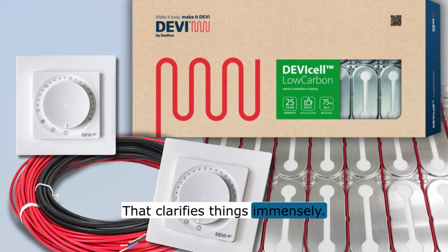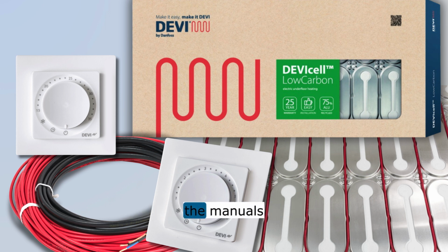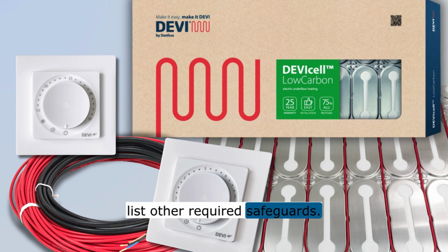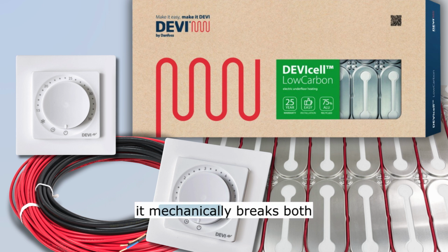That clarifies things immensely. Now, beyond the RCD, the manuals list other required safeguards. They mention the metallic screen wrapping the cable has to be connected to an earth terminal and an all-pole disconnection switch. Right, to pause on that switch for a second. An all-pole switch means it mechanically breaks both the live wire and the neutral wire at the very same time. So it completely severs the connection. Exactly. It ensures that when you turn the system off for maintenance, there is zero chance of any stray voltage lingering in the circuit. It's a total physical disconnect from the grid.